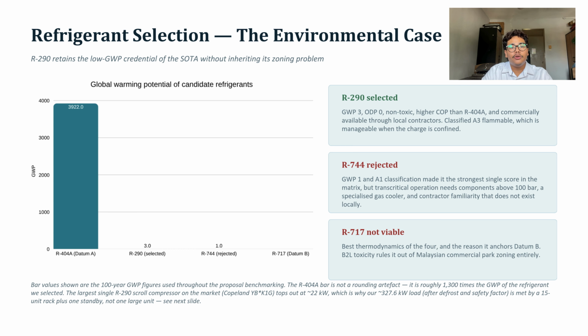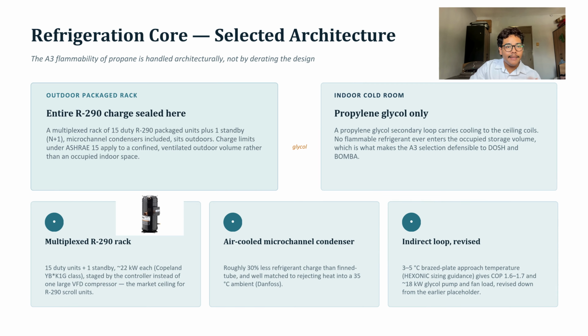So this slide shows in detail exactly how we manage that risk architecturally rather than derating the design. As you can see, this is the core refrigeration architecture, and it presents the most important safety decision in our design. The entire R290 charge is sealed outdoors within a multiplex rack of packaged units. By confining the refrigerant to an outdoor ventilated volume, we comply with the ASHRAE 15 charge limit. Cooling is delivered to the indoor ceiling coil via a secondary loop carrying propylene glycol. Because no flammable refrigerant ever crosses into this occupied storage volume, this indirect system makes the R290 selection defensible to the authorities.